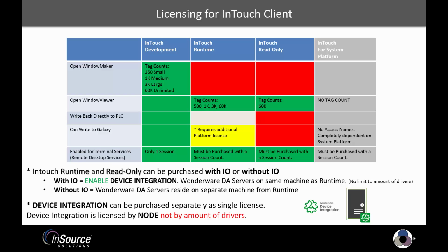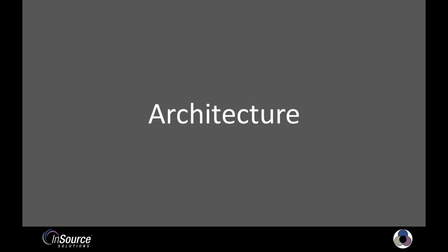Whenever we see tag count, whether or not it's development, runtime, or read-only, those tags are of all tag categories. Any tag that's an I/O tag, a memory tag, or an indirect tag is considered a tag that counts against your license. So let's look at some examples of how an InTouch application can be architected from a very small system and scalable to a larger system.